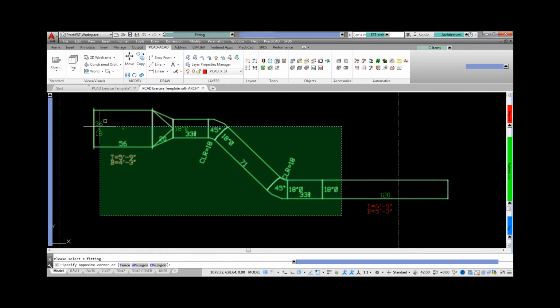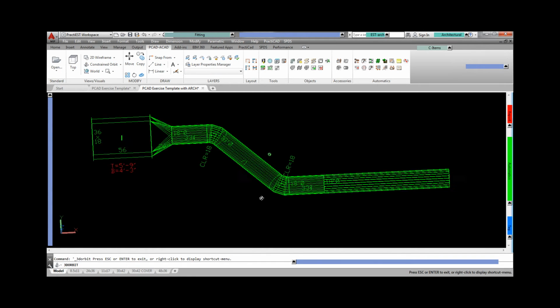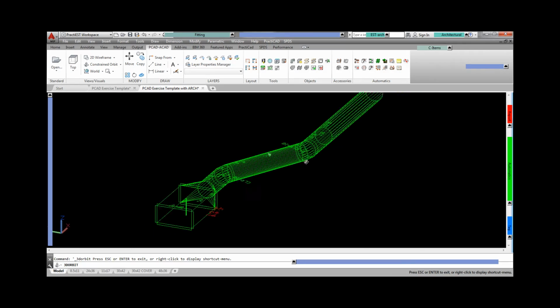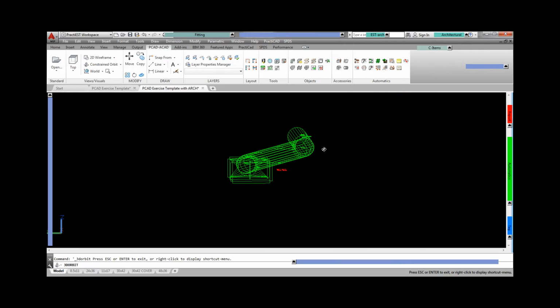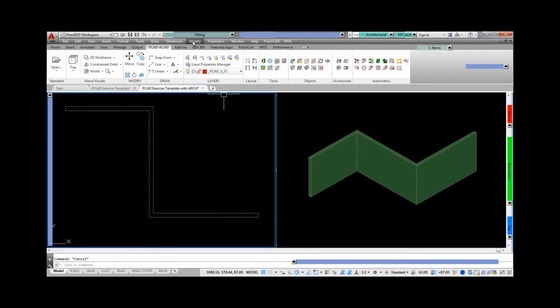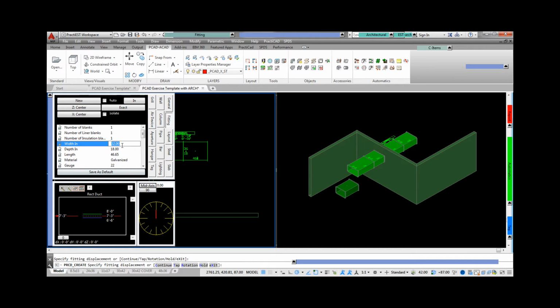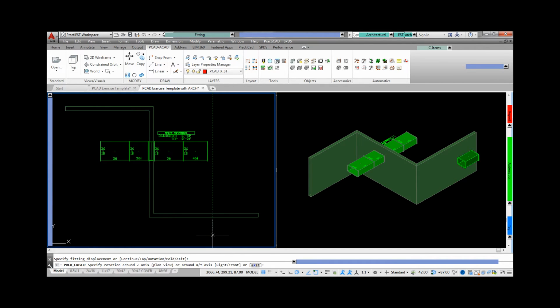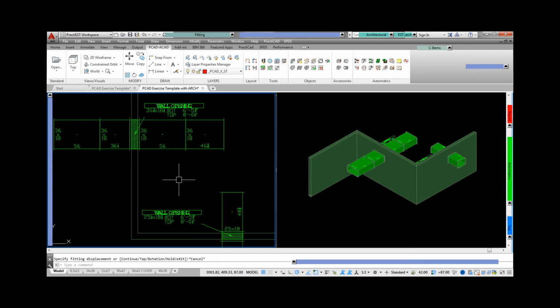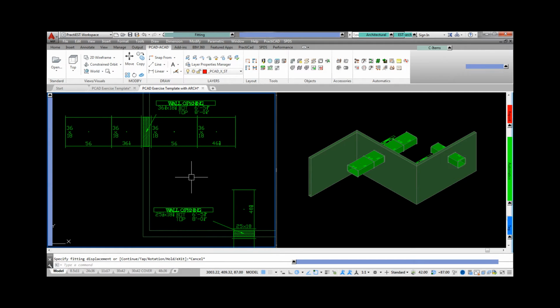Use auto-routing in conjunction with PractiCAD and you can see which of these scenarios is the most cost-effective for your shop. But the routing options don't stop there. We can create damper routes to automate the placement of a damper inside a fire-rated wall. Just grab a piece of duct, route through the wall. You can have the damper you want selected, positioned, the wall opening created, and the proper tagging to show your heights and opening size. This can greatly aid you in producing a fast wall opening drawing.